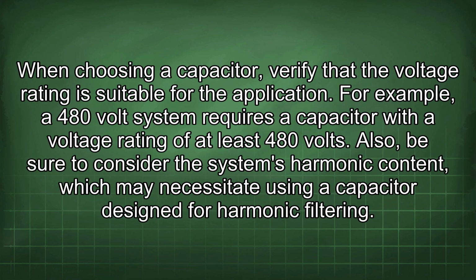When choosing a capacitor, verify that the voltage rating is suitable for the application. For example, a 480 volt system requires a capacitor with a voltage rating of at least 480 volts. Also, be sure to consider the system's harmonic content, which may necessitate using a capacitor designed for harmonic filtering.